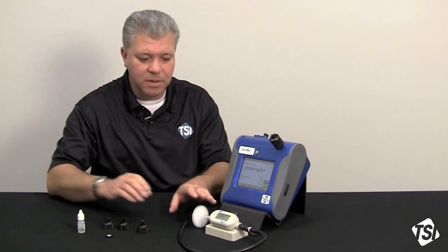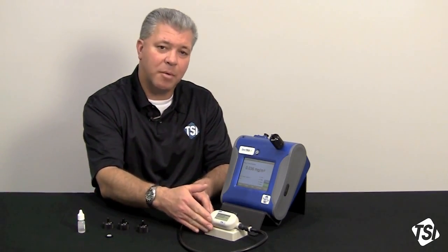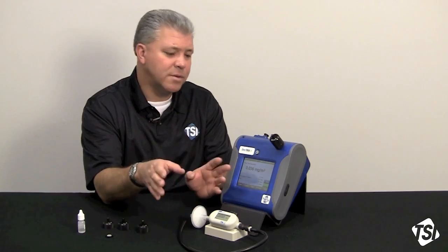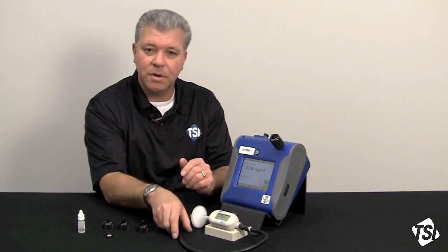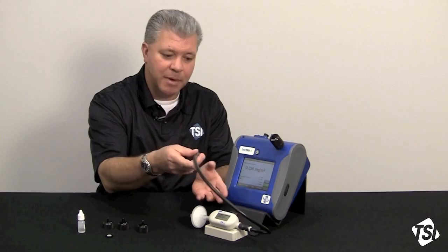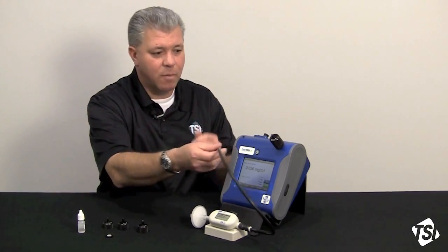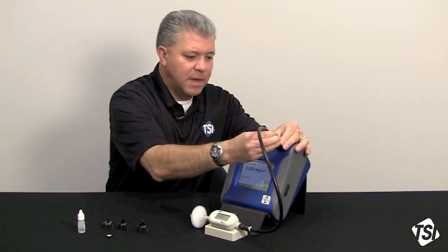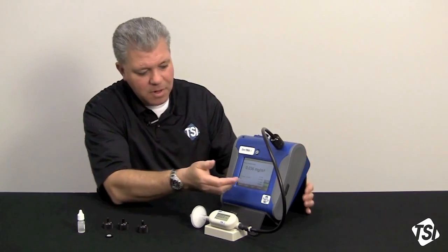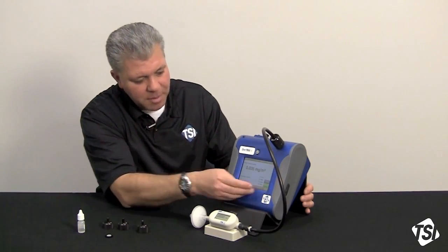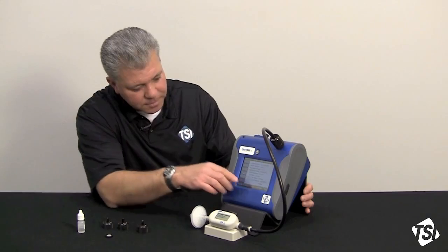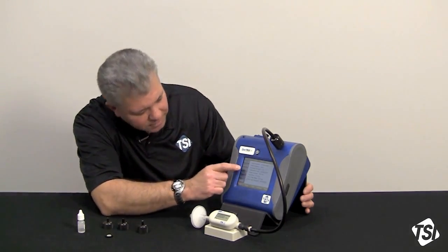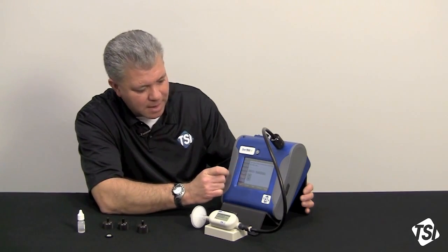So what we will need to do is to utilize an external calibrator to show us what that flow rate is. Any of the calibrators that are commercially available on the market are certainly acceptable. We're going to be using a primary calibrator from TSI today, a 4146 mass flow meter. I'm going to attach that to the inlet of the impactor, and then I'm going to go down to the setup menu and press the setup tab, and over on the right we get another row of tabs that come up, and I'm going to select Flow Cal. It's the second tab down.